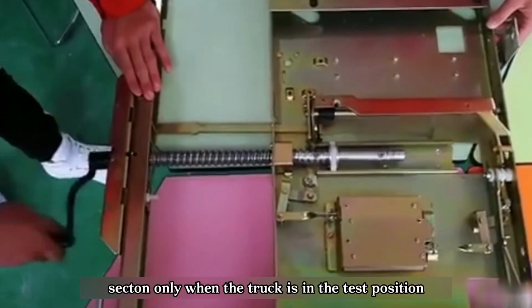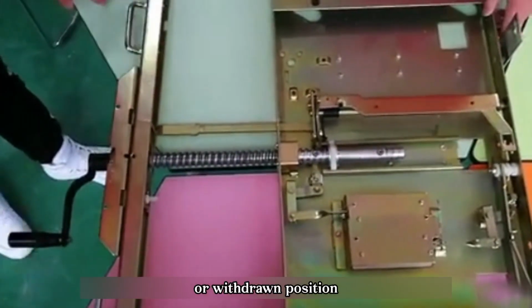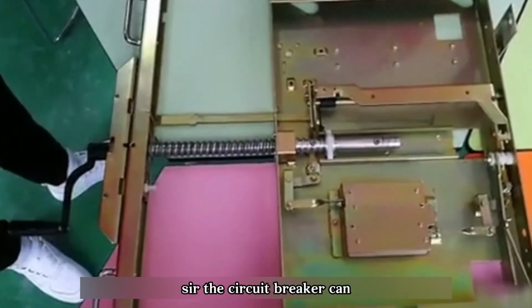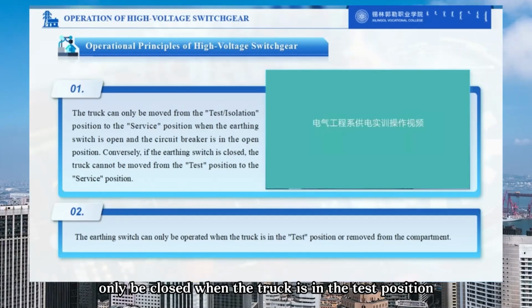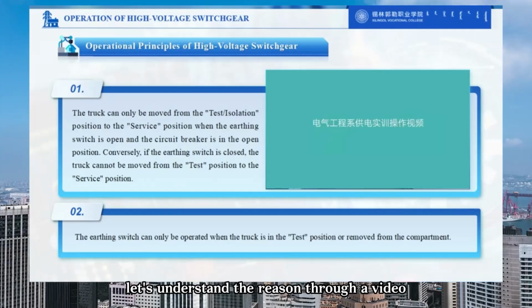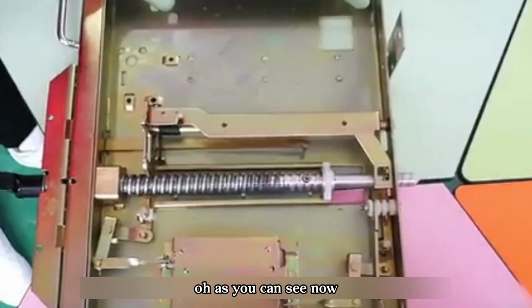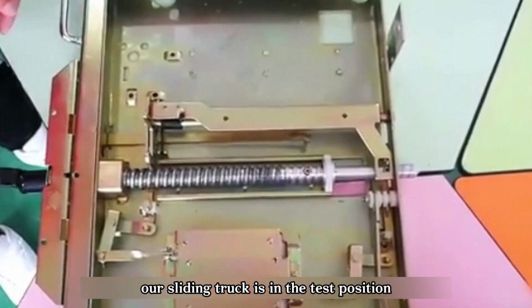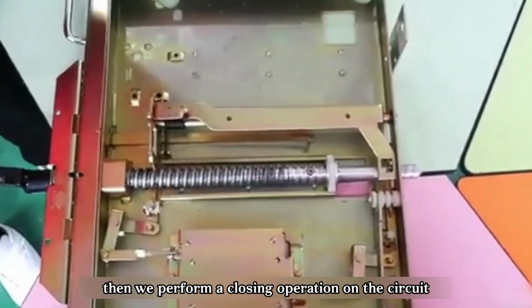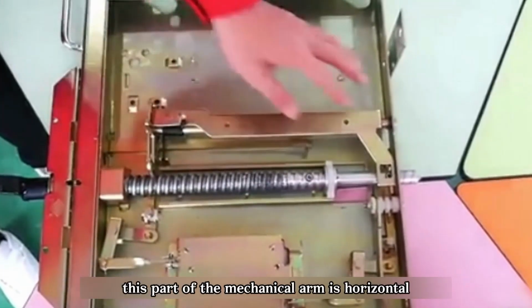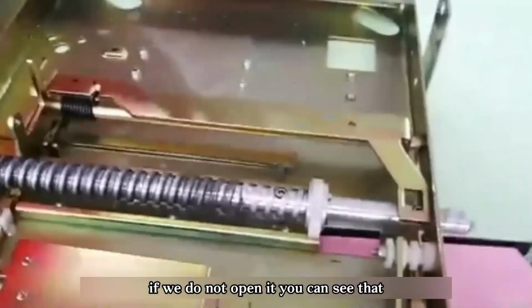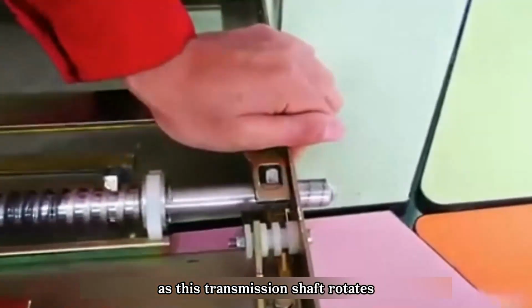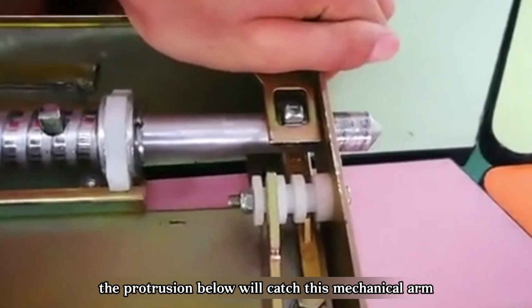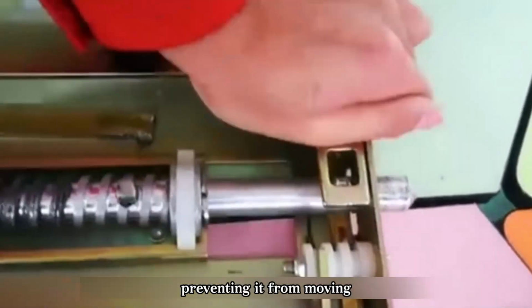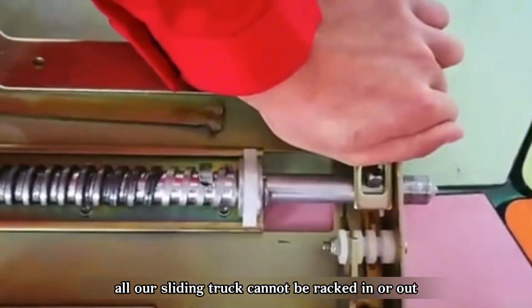Second, only when the truck is in the test position or withdrawn position can the earthing switch be operated. Third, the circuit breaker can only be closed when the truck is in the test position. Let's understand the reason through a video. As you can see now, our sliding truck is in the test position. Then we perform a closing operation on the circuit breaker afterwards. This part of the mechanical arm is horizontal. If we do not open it, you can see that as this transmission shaft rotates, the protrusion below will catch this mechanical arm, preventing it from moving. Therefore, our sliding truck cannot be racked in or out.